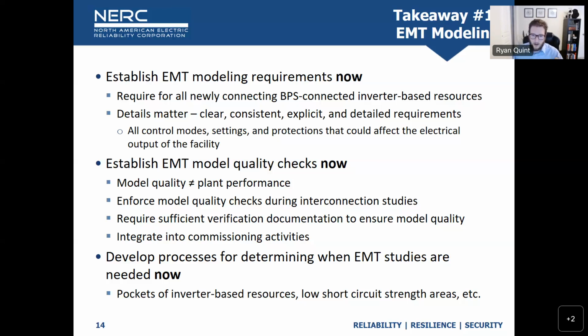Next, establish EMT modeling checks now, not later. We've seen that in the reports - for example, ERCOT has had EMT modeling requirements for many years now, but it wasn't until more recently that they established model quality checks and tests. So there's this period where models are being provided but not really checked, at least not rigorously. And so a lot of those models don't include most of the causes of most of the protections that would trip the facility, either in the inverters or in the collector systems, etc.